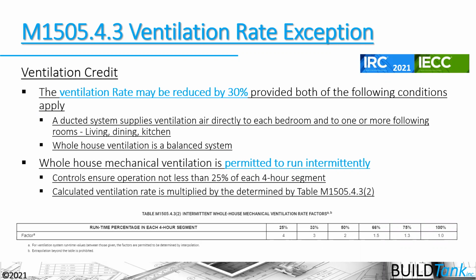So if I have a ventilation rate of 100 CFM continuously and I decide to run it 50% of the time, I need to increase the rate to 200 CFM. And the chart below helps you figure that out as well. So those are some things that we need to think about.